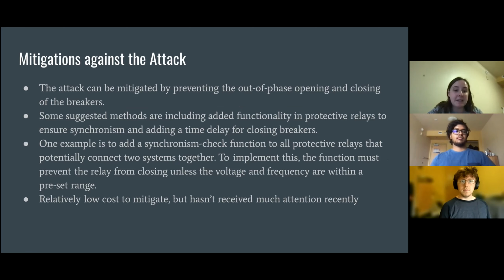Some suggested methods are adding increased functionality in protective relays to ensure synchronism, and adding a time delay for closing the breakers. One example is to add a synchronism check function to all protective relays that potentially connect two systems together. To implement this, the function must prevent the relay from closing unless the voltage and frequency are within the preset range. In theory, this could stop the attack.